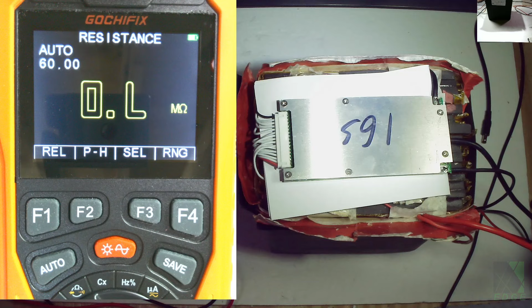In order to troubleshoot a battery like this, the first thing I would do is switch the voltmeter to voltage, so we'll go to the voltage range, DC. When troubleshooting a battery like this, it's a relatively large battery, and if you make a mistake and probe the wrong place, it can really cause a lot of problems. So I always put the shrouds on whenever I can. Now, at the top of the battery, there's this kind of ribbon cable with all these connections. These are going to all the cells, and these are all the monitoring and probably balance wires used by this BMS. Then you have some other wires.